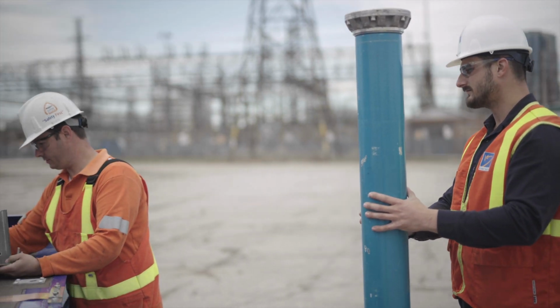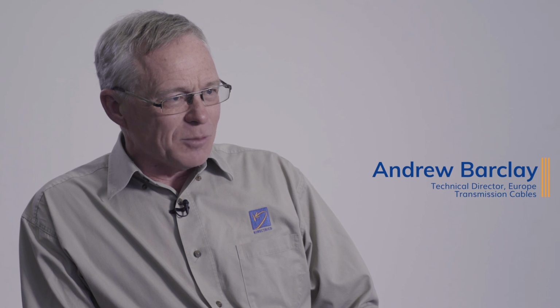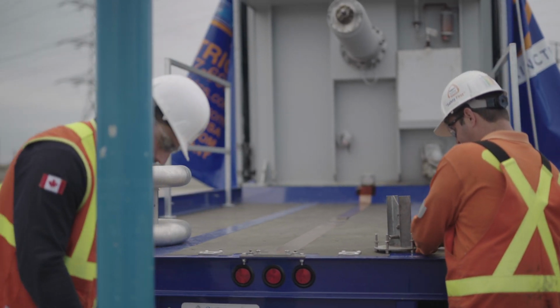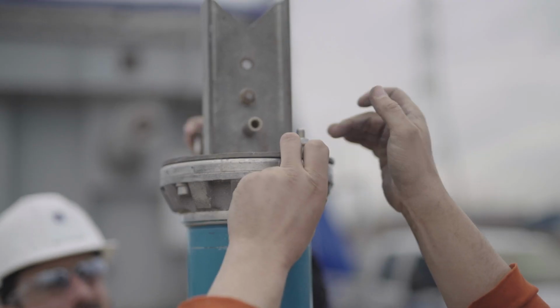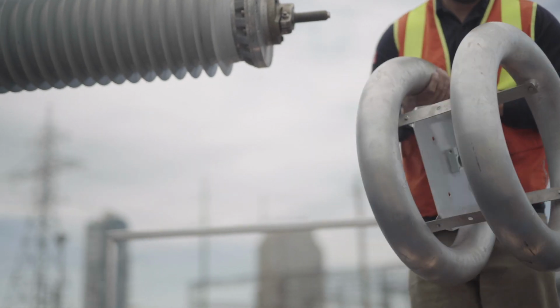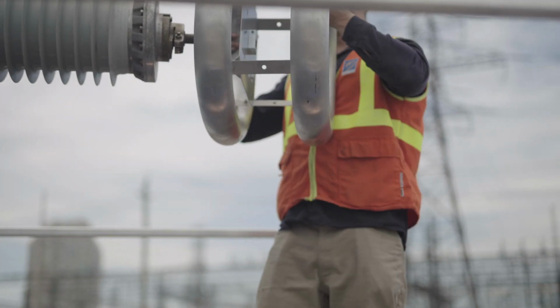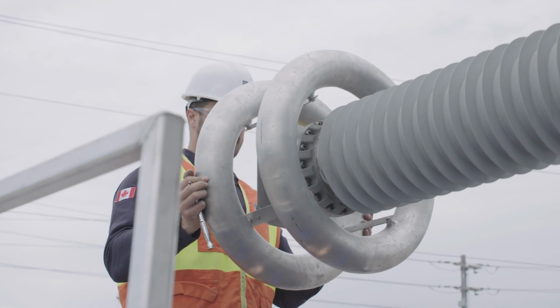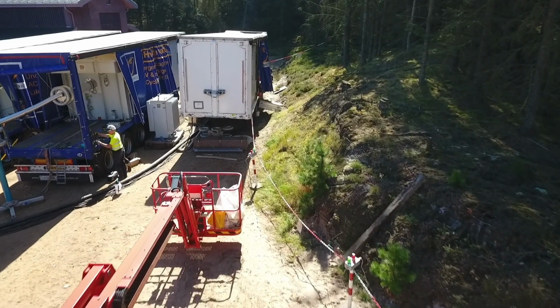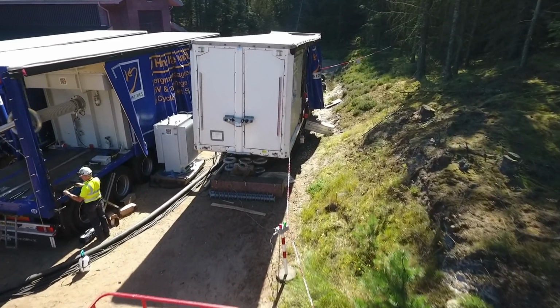Now, it's important to screen those defects out during the commissioning stage rather than in service. It's not just a headache, but a major financial blow to the owner of the power station and probably to the network operator as well, due to losing all that revenue. Think about it as going to the doctor and then you check your heart. You don't want to check your heart rate only, you want to check a whole bunch of activities in your heart. These are the same scenarios for cables. So you stress the cable to uncover the defect, somebody fixes it, and then you turn around and you retest again to make sure the defect is gone.